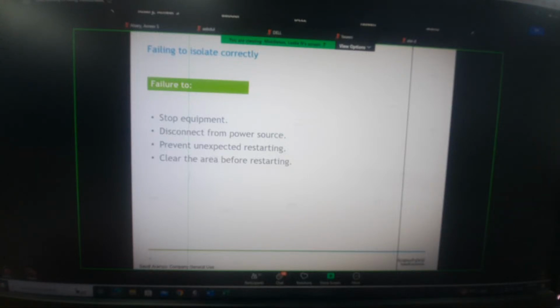There are several fatal mechanisms that are contributing factors for injuries that are caused by failing to properly isolate. Failing to stop or isolate equipment, failure to disconnect from the power source, failure to prevent unexpected restarting, failure to clear the area before restarting, and failure to provide suitably trained personnel and the correct required PPE.